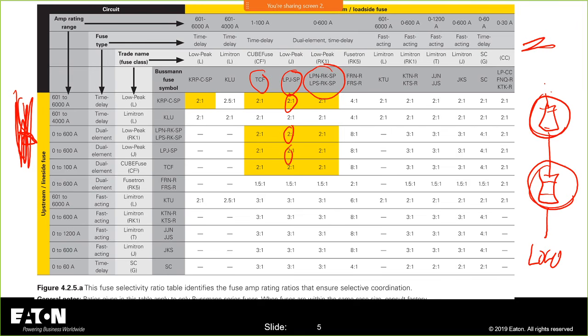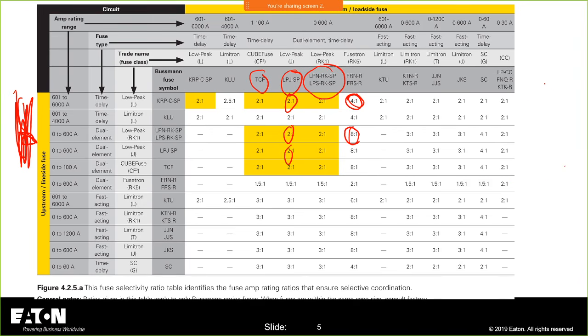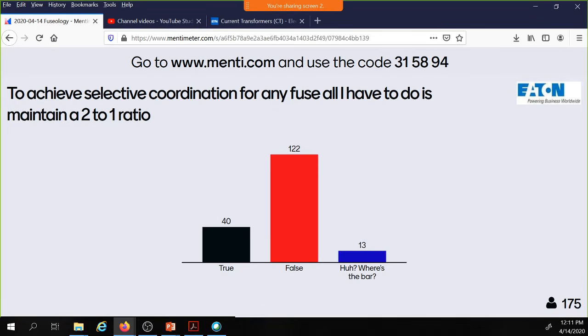There are some 8-to-1s in here. There are some 4-to-1 ratios, depending upon what you have upstream and downstream. Now, if you just jump into a certain type of fuse, class or family, then you're pretty much safe. But just keep in mind that for these tables, not every fuse is 2 to 1. You do have to be mindful. So the right answer here is false. So 122 of you can stand up from your chair, pat yourself on the back, turn around 3 times, and sit back down. Thank you very much.